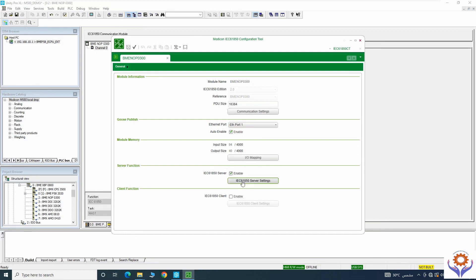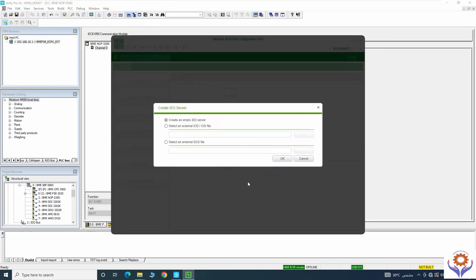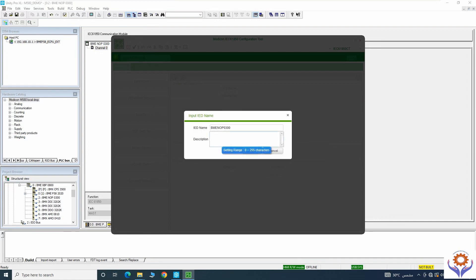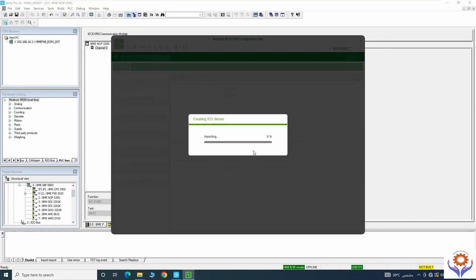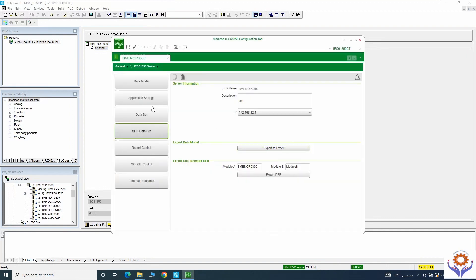Now we are going to check the server function. I enable the server function, double-click, and it asks to create a new IED server. I click OK, then give a description — I will put 'test' and click Add, then OK. See, it is importing — the file is open with sections for data model, application settings, data sets, report control, GOOSE control, and external references.